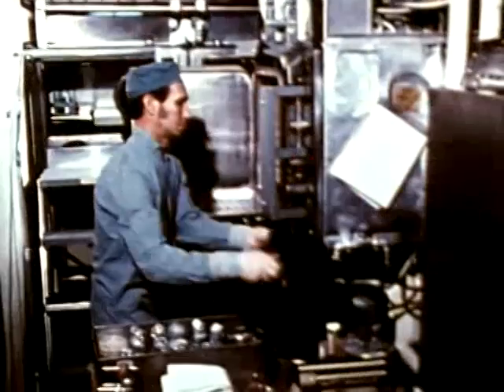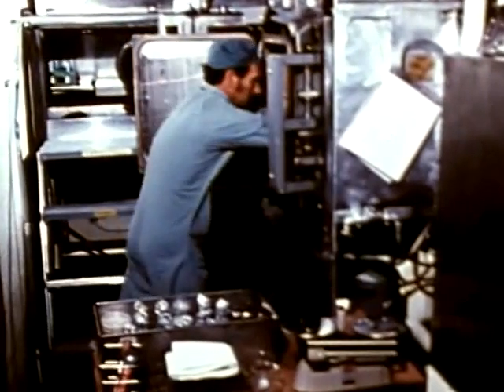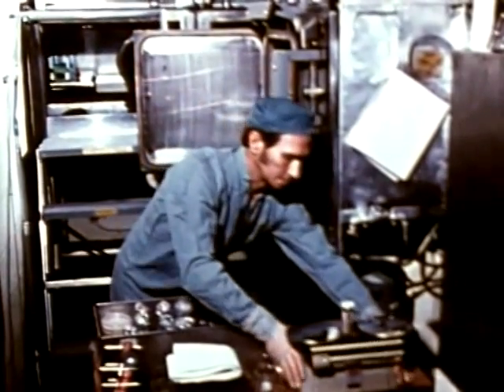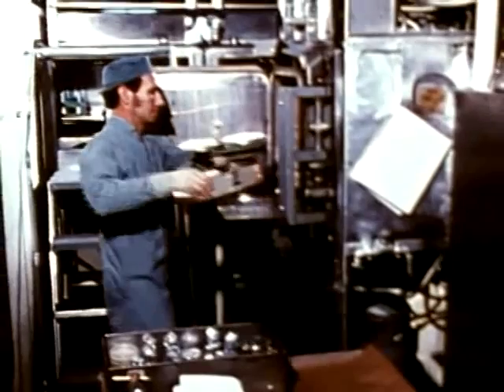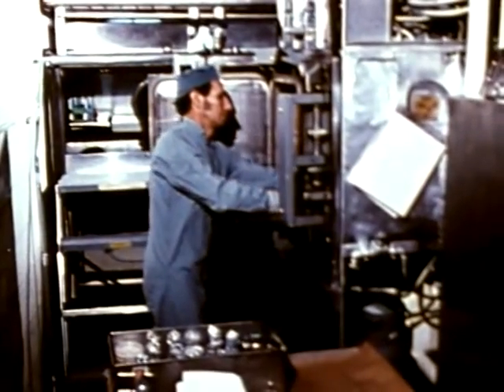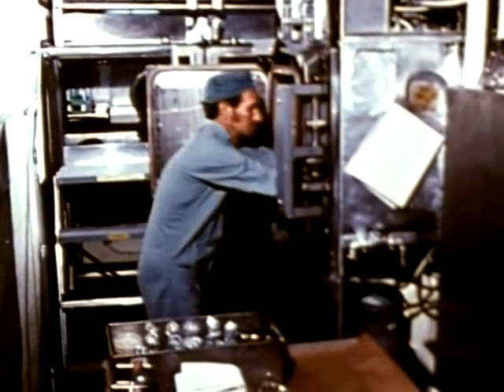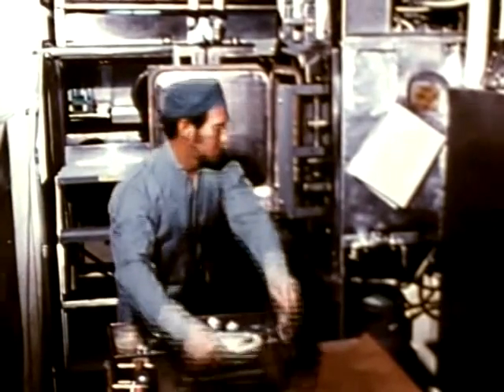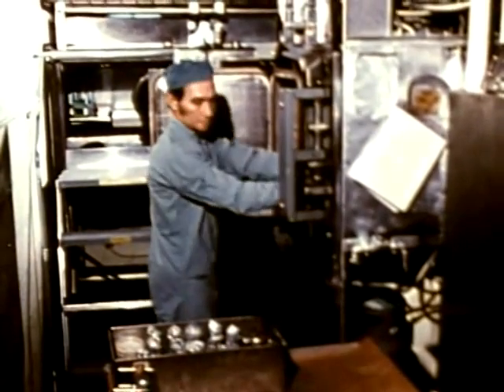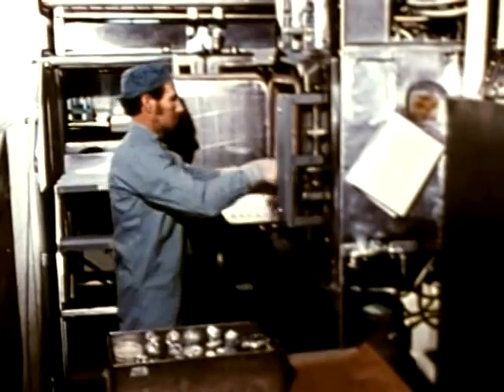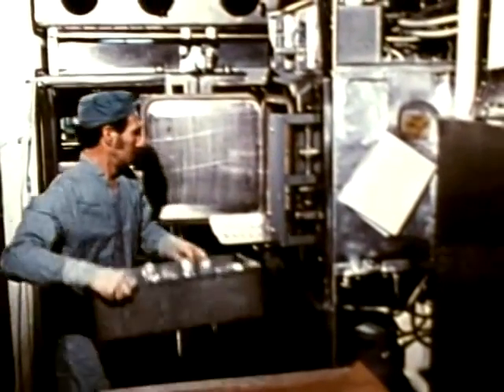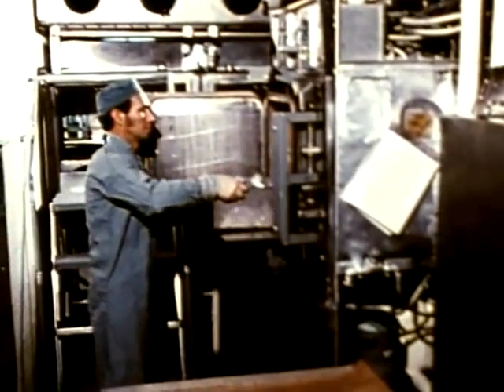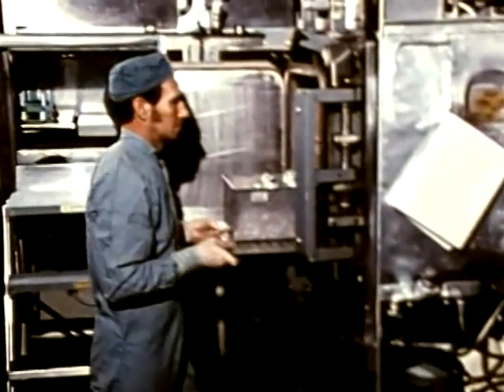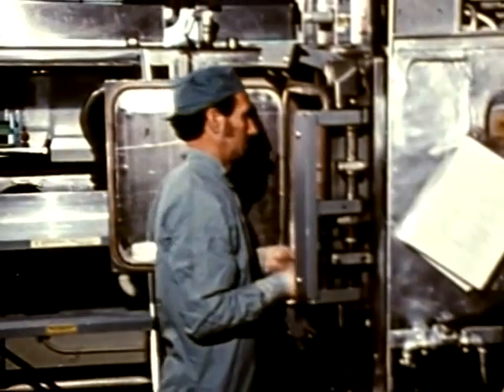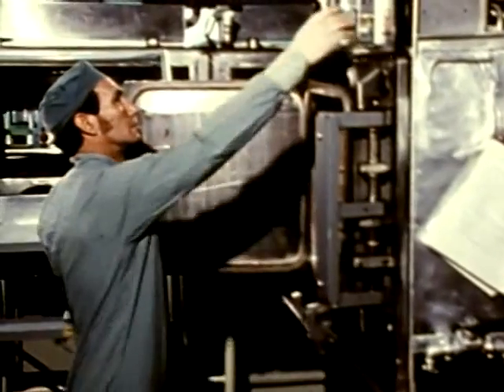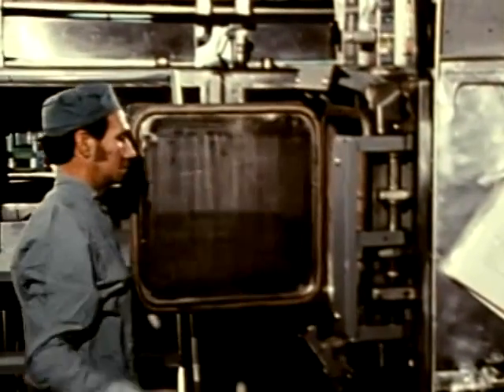Each experiment must be carefully planned, well in advance, since all of the materials used in the experiment, including chemicals, cultures, and laboratory equipment, must be brought into the group of interconnected cabinets, or cabinet line, as it is called. One of the methods of bringing materials into the cabinet is through an autoclave or steam sterilizer. Equipment and materials are loaded onto a shelf inside the autoclave for transfer to the interior of the cabinet line. A heavy door is then swung into place and locked to provide a tight seal.